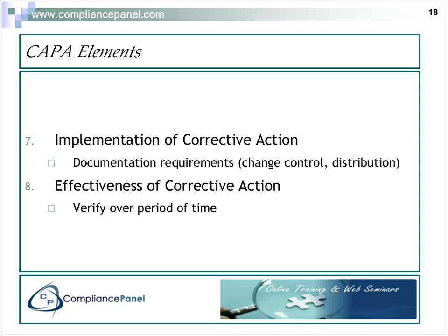Something that I've implemented for quite a while now is that in each of our quarterly quality review board meetings, we take a look at recently implemented corrective actions for the past quarter with regard to in process or field reports, whichever is applicable. And we say that for the first quarter, there were 9 complaints, for example, on products made before this corrective action was implemented, but 0 products made after the corrective action was implemented. And once we have 4 quarters of no complaints, field reports that is, alleging the same nonconformance, we consider that corrective action effective.